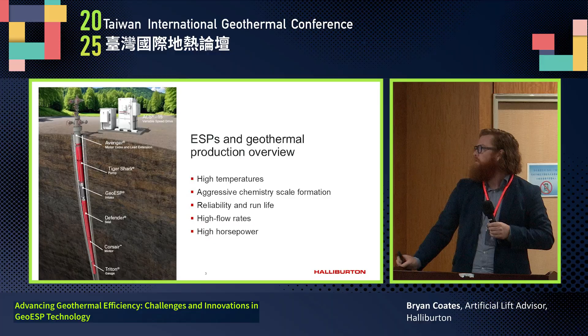The benefit is they also lift from very deep wells. We can go 1,000, 2,000, 3,000 meters of lift, no problem. They still run efficiently — the pumps themselves these days are getting up over 80% efficiency, and motors with PMMs are looking at 90 plus efficiency. It makes for a really efficient system to lift fluid out of the ground.